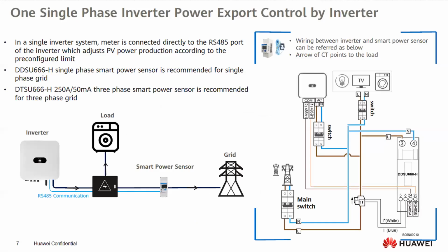And then since this system can be interconnected with a grid, definitely you need a grid meter to monitor your export and control. In cases where you are not allowed to feed in, then you can control for export limiting. So Huawei inverters come with a smart meter, which is a Chint DTSU666-H. It comes with its own CTs, which are 250 amp primary winding. I'm sure in residential you won't get that far. Most residential inverters are around 60 amp, max 100 thereabout, right?